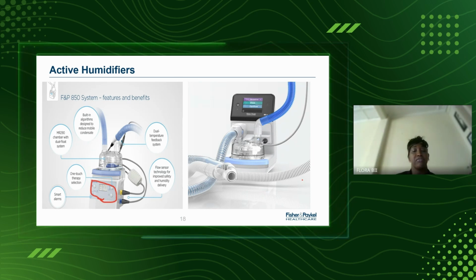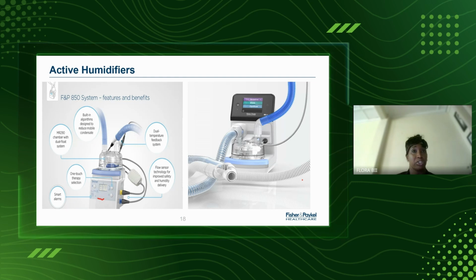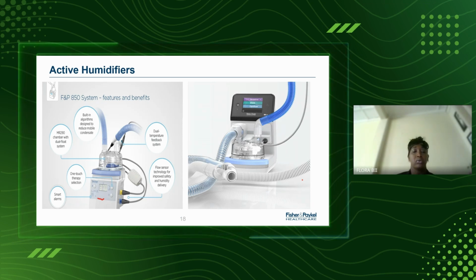Why this is important is if it is in invasive mode for, say, a neonatal patient, it would be almost a standard of care practice to ensure that the neonate is receiving 37 degrees centigrade, 44 milligrams per liter of humidity, just as Joanne mentioned earlier. So it would always be on invasive mode. However, there would be instances where you'd be offering BiPAP or even CPAP, or a mask mode where you'd be using an NIV mask. So because of that, you toggle this button to be able to guide the humidifier on the amount of heat that it would produce in that regard. There's also the power button and the silence button. So this is what would comprise the display unit.